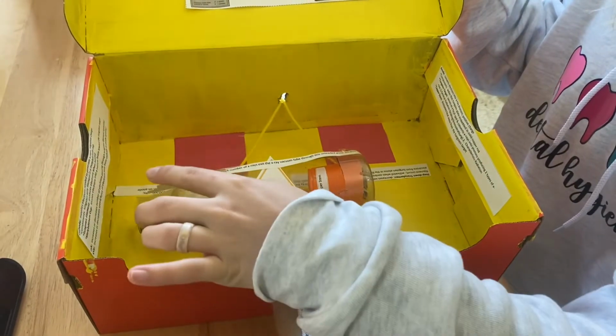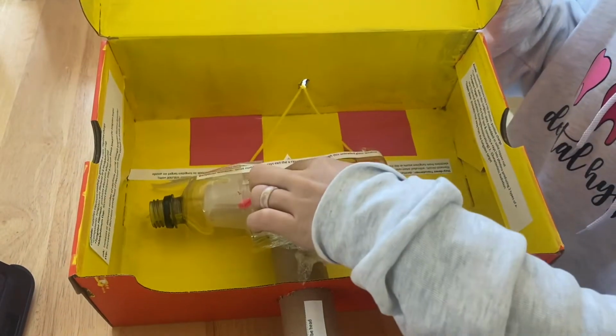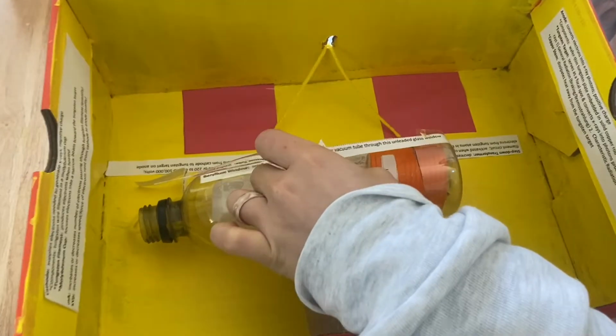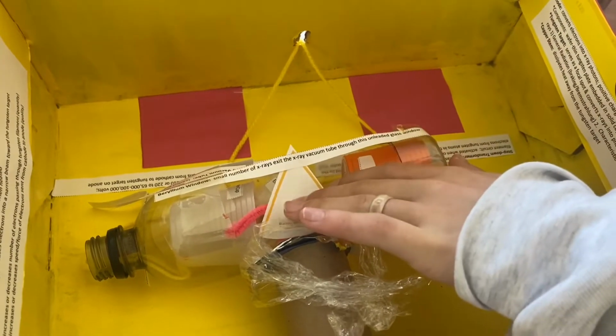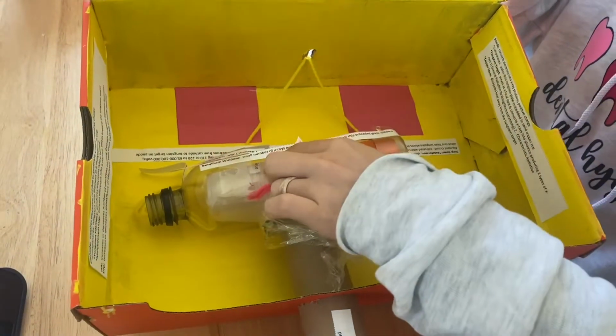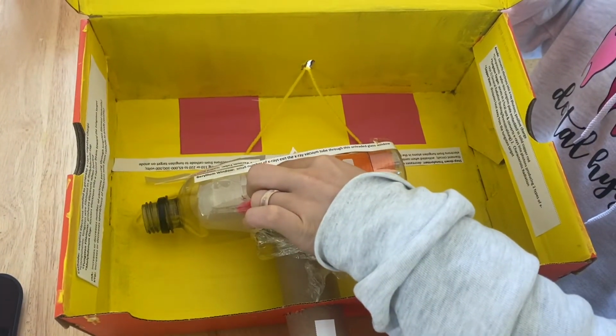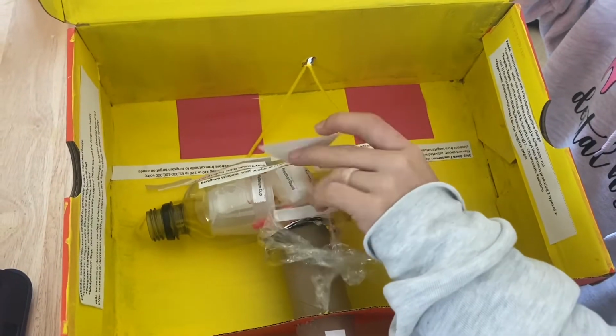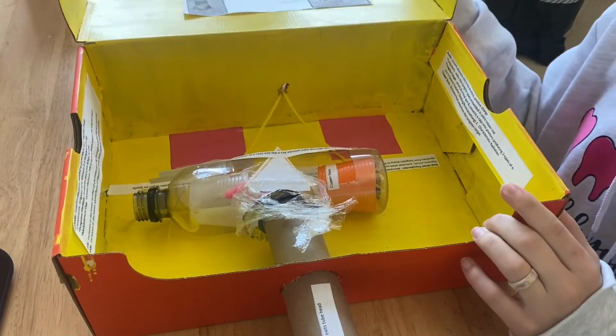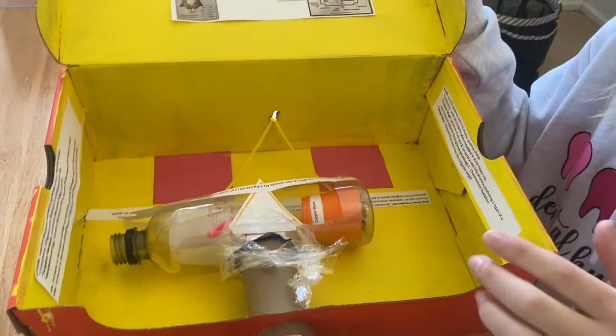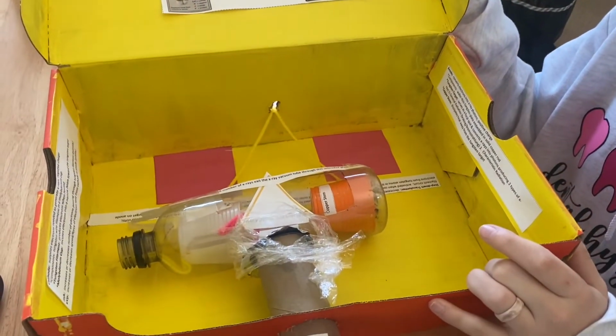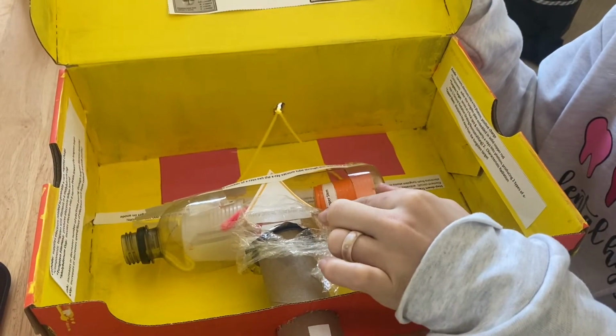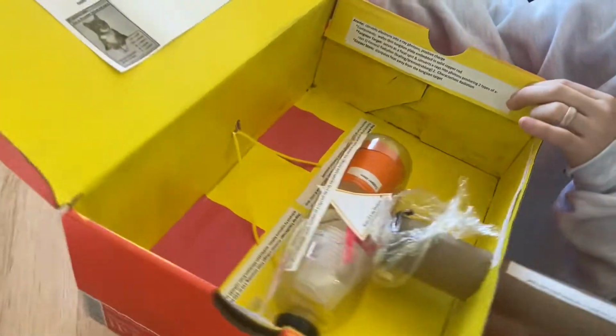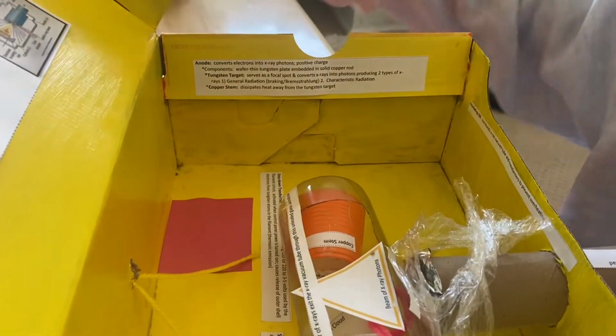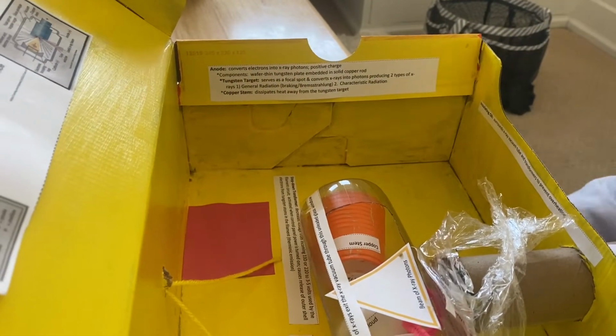Okay, so these electrons are now in a state of excitation as they hover around this tungsten filament under here. I can put this up. This tungsten filament right in there is actually recessed in the molybdenum focusing cup, which is represented right here as well. So the line current enters the cathode anode high voltage circuit, and the step-up transformer over here will increase the voltage, which will impart sufficient force to propel free electrons towards the focal spot on the target at the anode. We've got the anode represented over here, which converts electrons into X-ray photons, representing a positive charge.